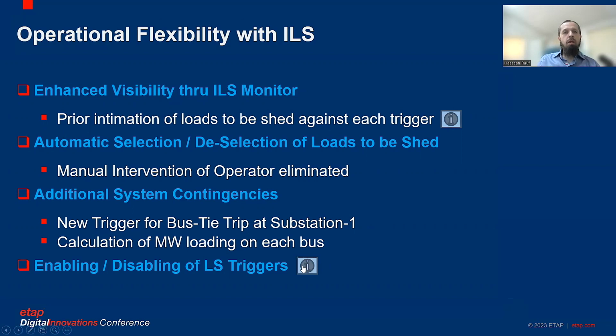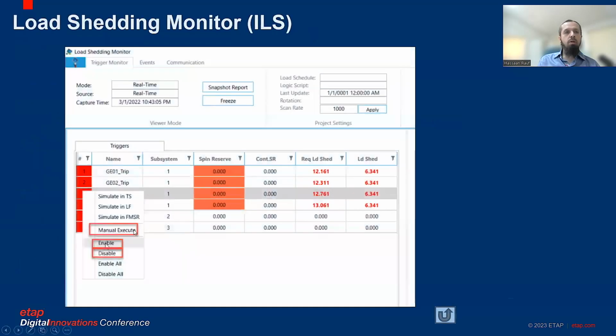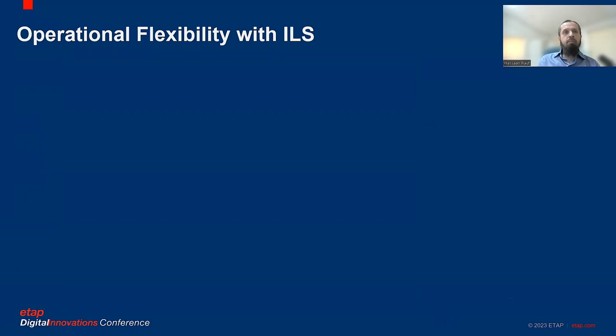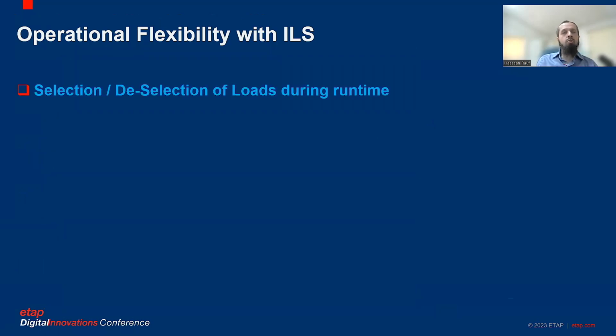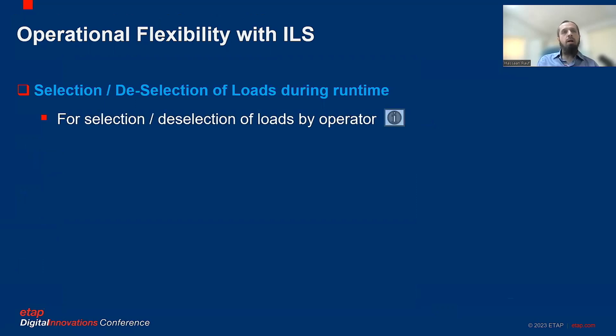Another advantage was enabling and disabling of load shedding triggers. This was available to the operator during runtime. He can enable or disable the trigger, as you can see in the screenshot. Then, selection and deselection of loads during runtime. This was a requirement of FFC that during runtime, the operator should be able to select or deselect a load for any of the applications, for any of the process conditions. That feature was originally not available, but during the implementation phase, ETAP provided us with updated software, and this requirement was also fulfilled. Otherwise, normally the load configuration is done in a separate configuration manager, which is only accessible to engineers. But for the selection and deselection part of load, that was also provided to the operator.